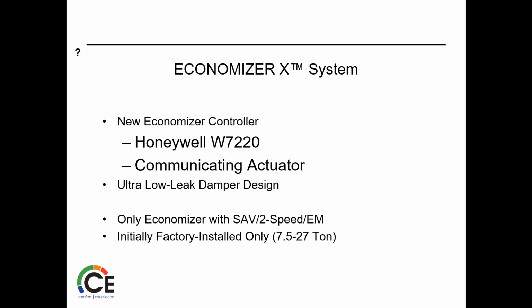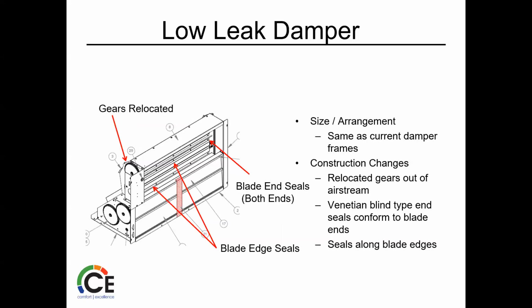So, a couple trade names here, just test questions, hint, hint. Factory installed only, initially factory installed only. Now you can get a field installed. Low leak damper, gears are relocated to the rear side of the damper housing. It has a notch blade that ends are now square cut and seal on the flexible seal. So that's kind of where we're trying to keep the leakage down a little more, so we'll just change the design of that a little bit.